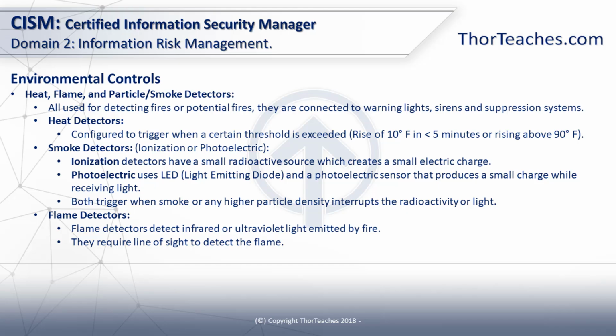It's common to have people in the data center 24/7, or at least in an office close to it so they can monitor the equipment. If the alarm sounds, one employee will go into the data center to see if there is a fire or not, and the other will stand next to a turn-off switch, where there's a little button they have to hold in, and that will delay the fire suppression. As soon as they let go of it, if the timer has been reached, either the fire suppression will trigger, or the countdown will start again. 20 seconds later, the fire suppression will go off.